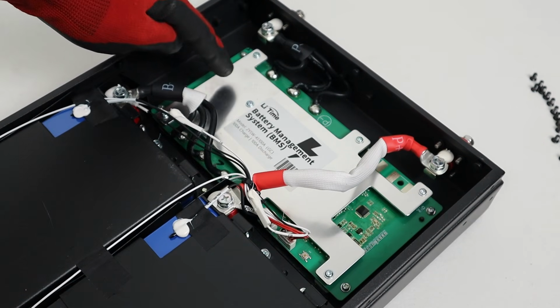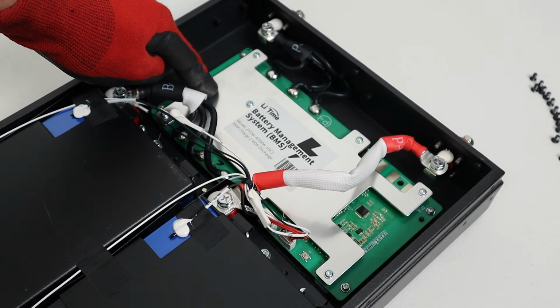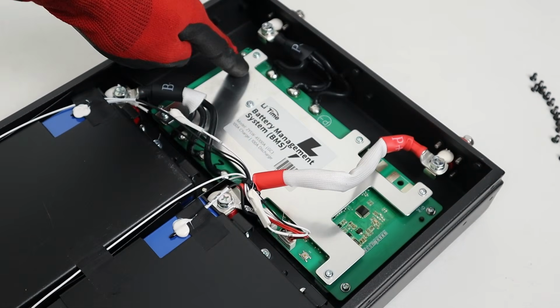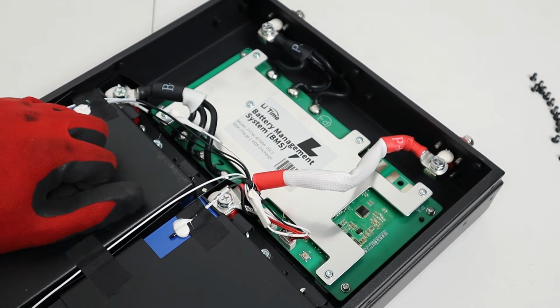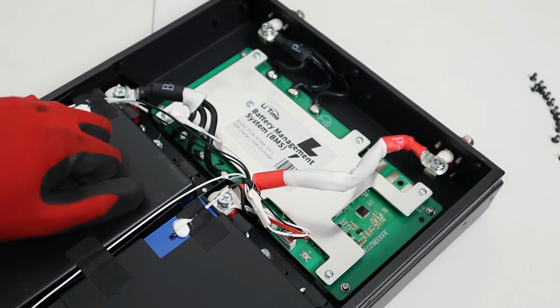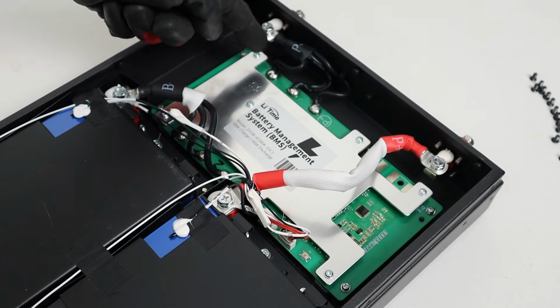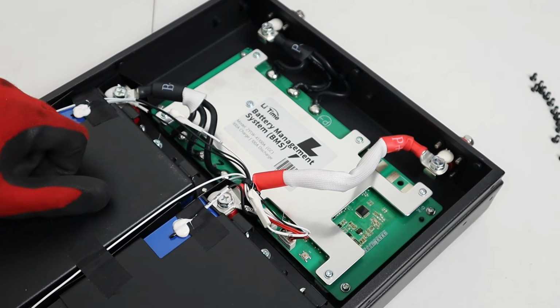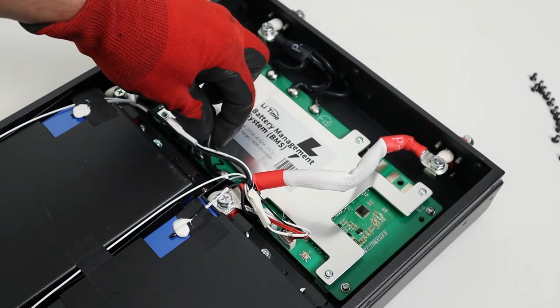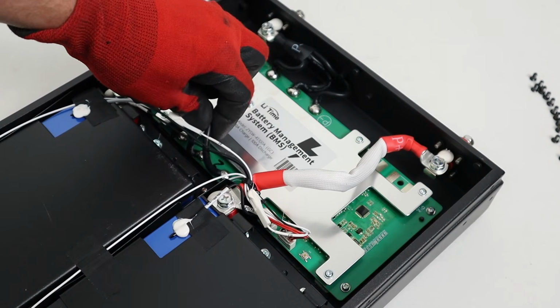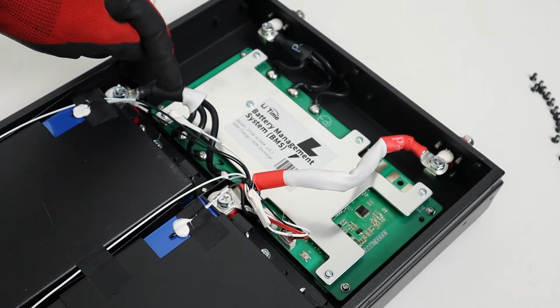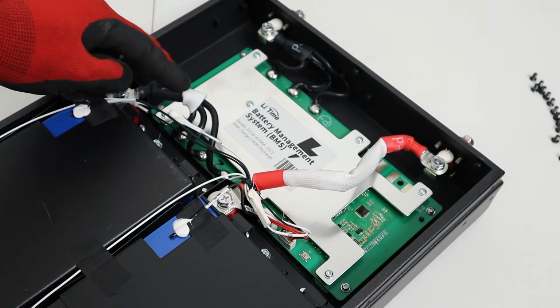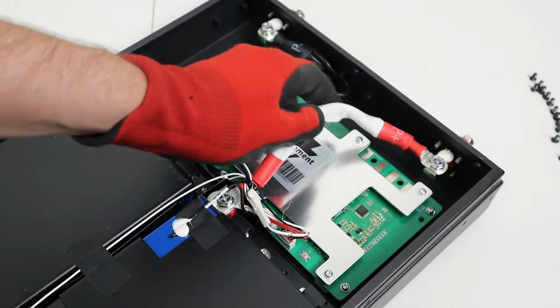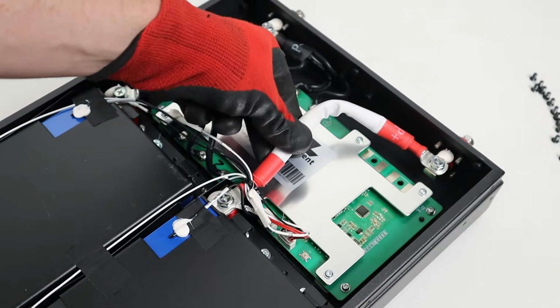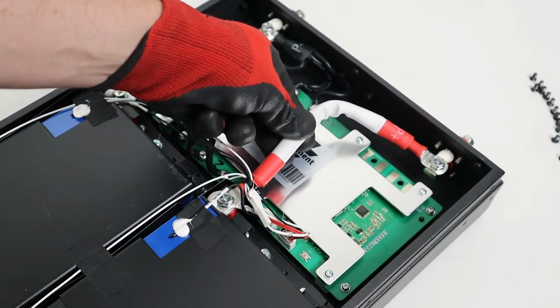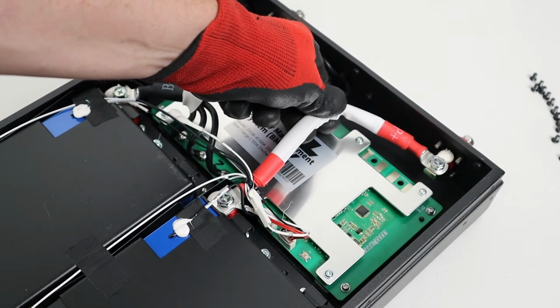It has a heavy duty heatsink on top, and you'll notice they're using soldered connections here. Would have liked to see screw terminals, but it looks like they're soldered very well on each side. As for the conductors, it looks like they're using 3 10-gauge wires going through each side of the BMS. The positive conductor feels fairly large — I'd say this is probably a 4 or 6 gauge cable.